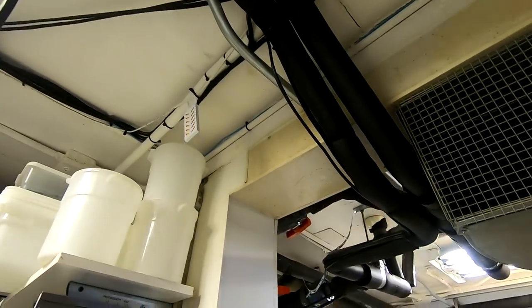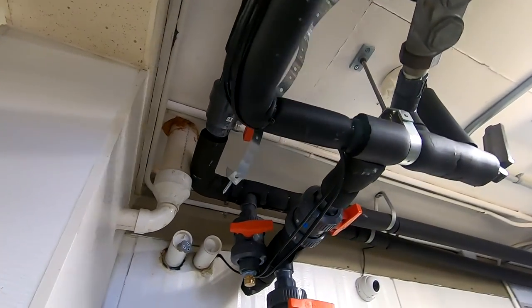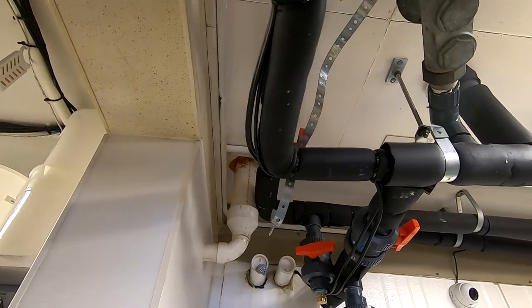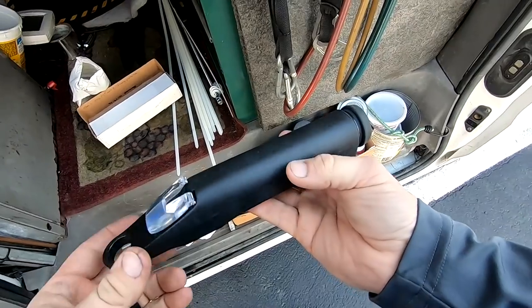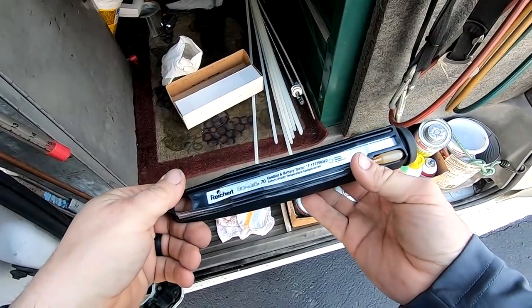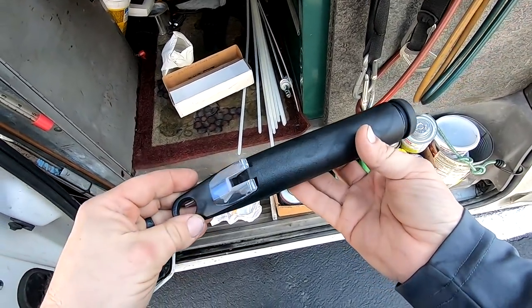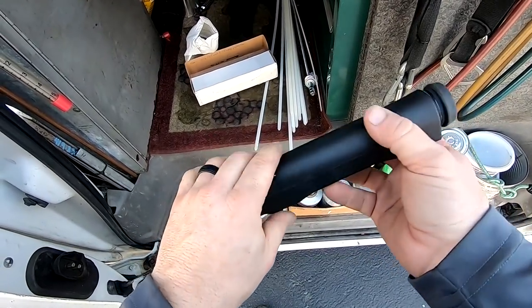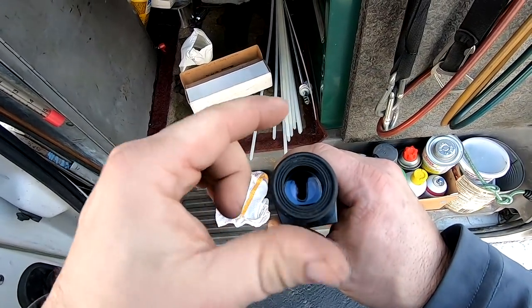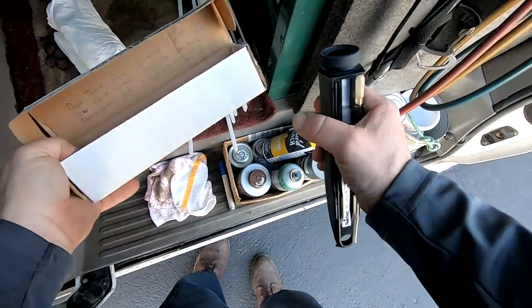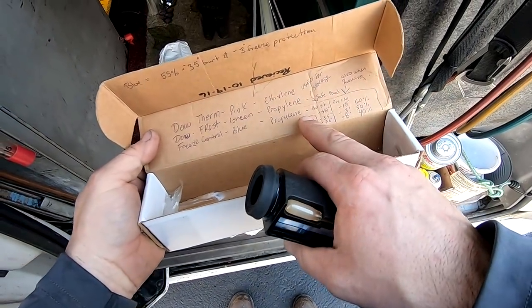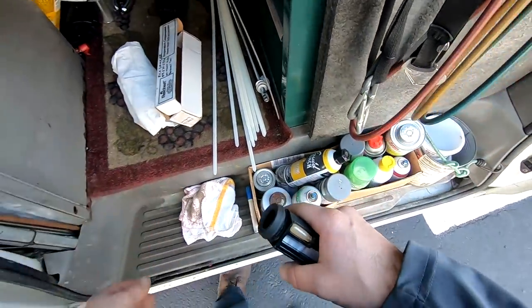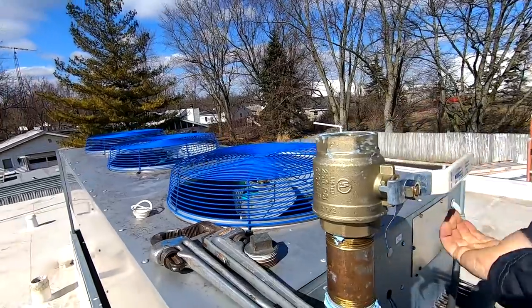And now we're up on the roof and we'll open that up there and we'll let the circulator do its job. And then we'll check our freeze protection and see where we're at. This little gizmo here is our refractometer. And basically this is how we're going to check it. Put a little bit of the blue whatever it is you got there, look through it and then you can see what your value is. The blue stuff, which is Freeze Control - that's the brand of it - there's a chart on the side of the bucket for that one there.